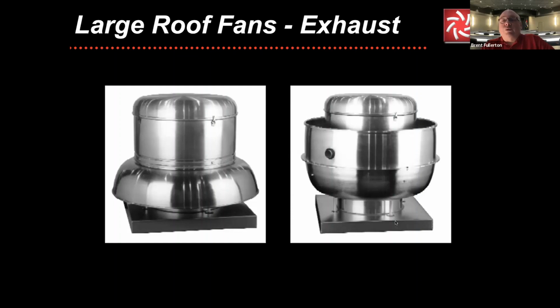Additionally, it does cost more because there is more material. So going right in here, and as I always like to refer to it, pulling the lever on the slot machine after you dropped your coins in, you've got your CFM and static pressure, and you've got those selections right up there in the wide range. So you can see both styles, the down blast style and the up blast style. Now you can see the relative costs, you can see the budget price, but you can also see the brake horsepower and even the sound.